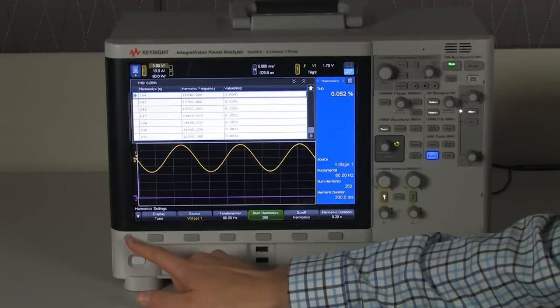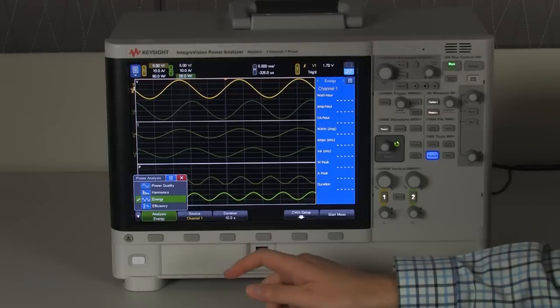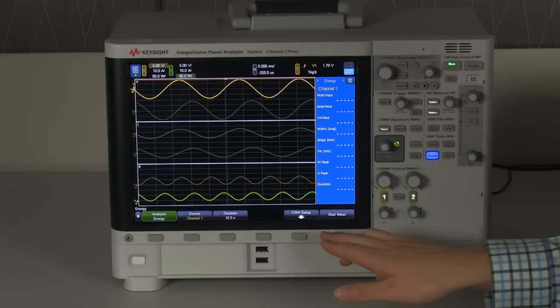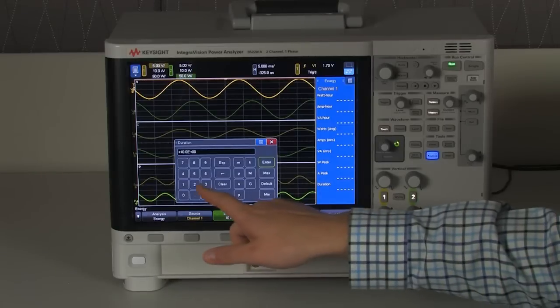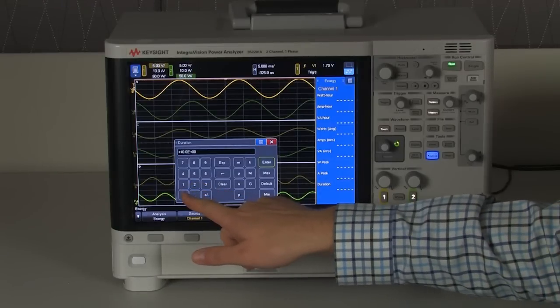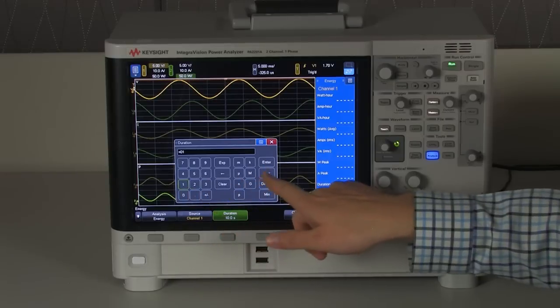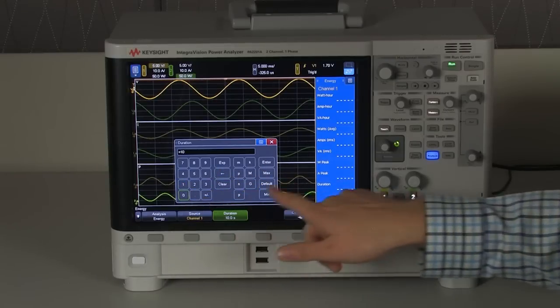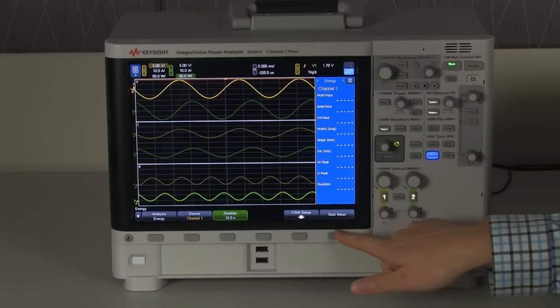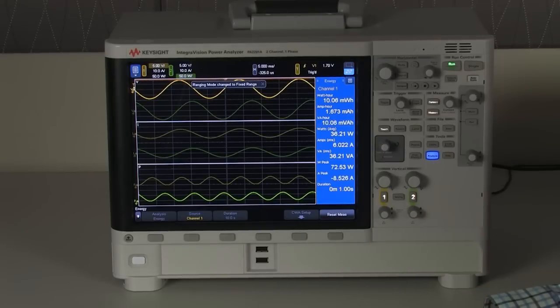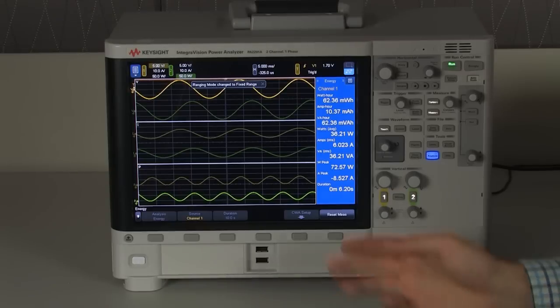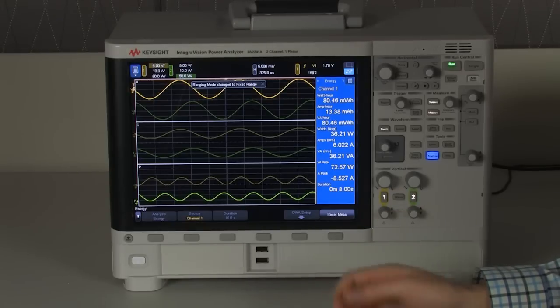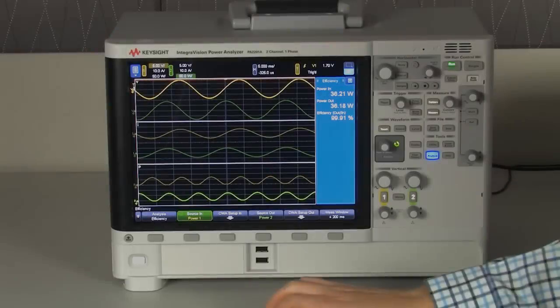After our harmonics menu, the next thing we can do is energy measurements. In this case, we can set up how long we want to do our energy measurement for. Let's say I want to do it for 10 seconds. And I can start the measurement. And after 10 seconds, I will see how much power I consumed in that time. This can be configured up to as much time as you're going to possibly need for energy measurement.